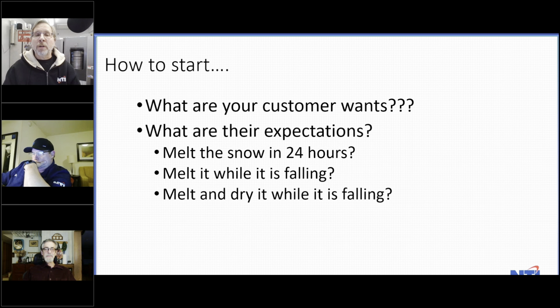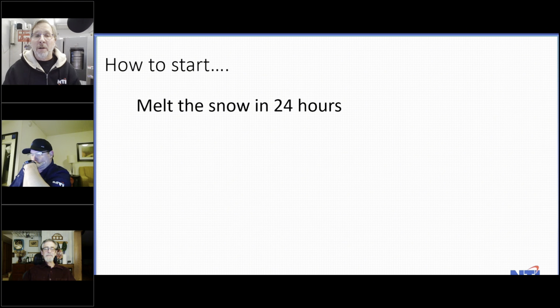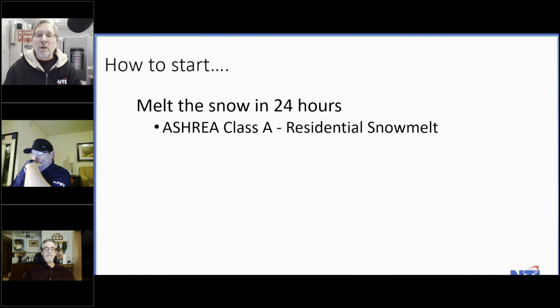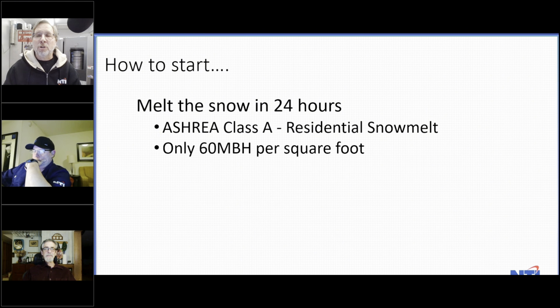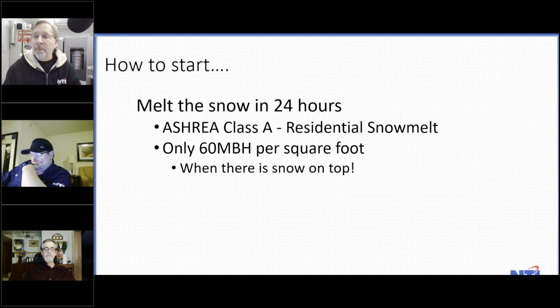Yes, these are the three levels of ASHRAE standards written in the code books, folks. Snow melt in 24 hours — that would be a Class A residential snowmelt, only 60 BTUs a square foot that you figure on, and that's based on when there's snow on top. If there's no insulation on top of your slab — your driveway or snowmelt area — it's giving up over 250 BTUs a square foot trying to heat the stars out in the universe. So please, if there's no snow, you're going to waste heat. Trust me on this.